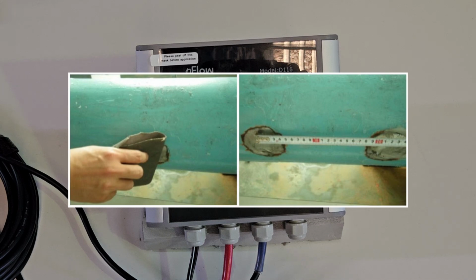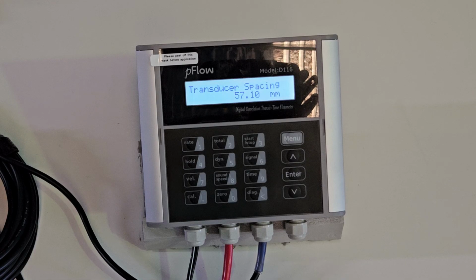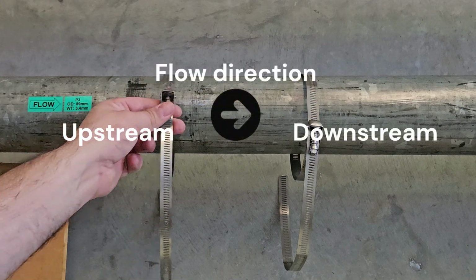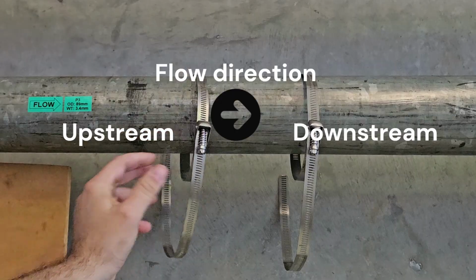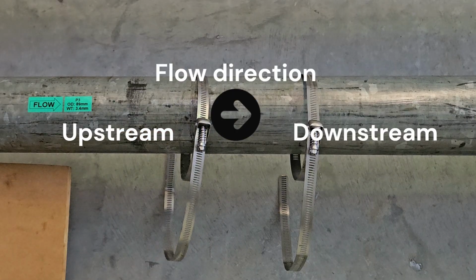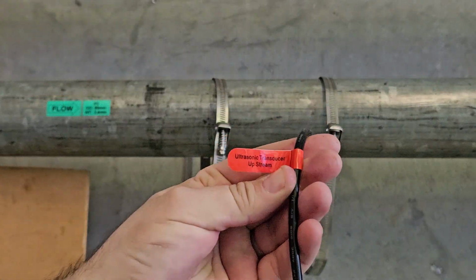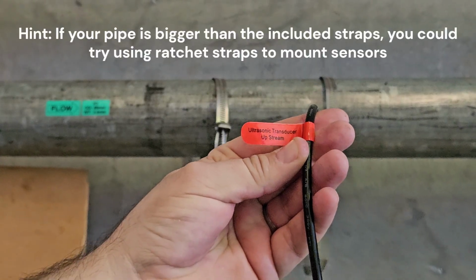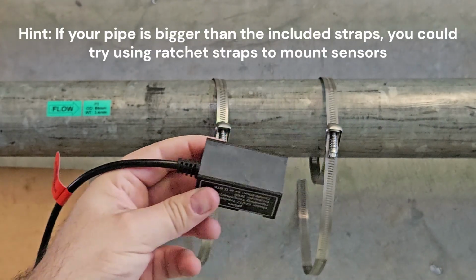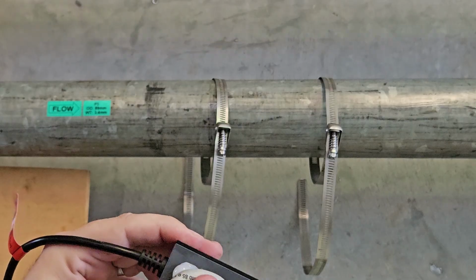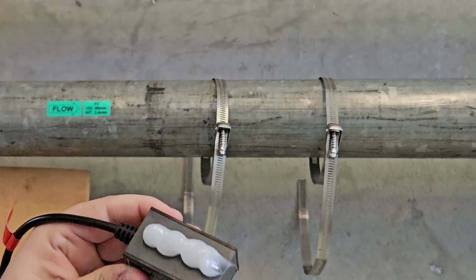bare pipework. Now take the pipe straps and prepare them on the pipework, wrap them around the pipe and set up as much as possible to ease install of the sensors. I am first installing the upstream sensor. Take some couplant and apply a blob on the sensor surface. Use enough to cover the whole surface once it's squished onto the pipe.